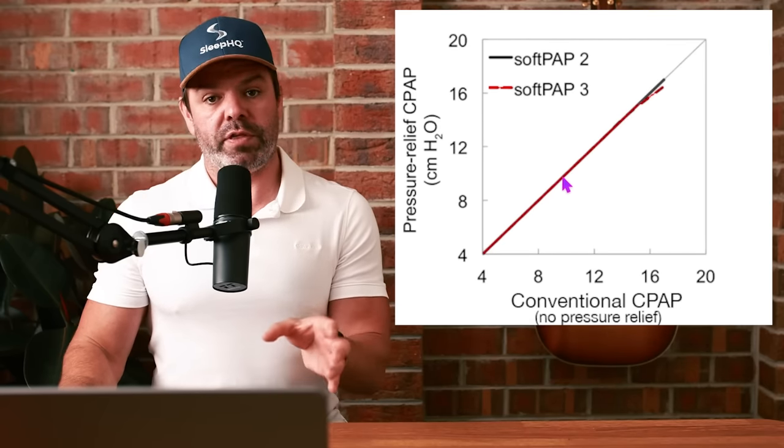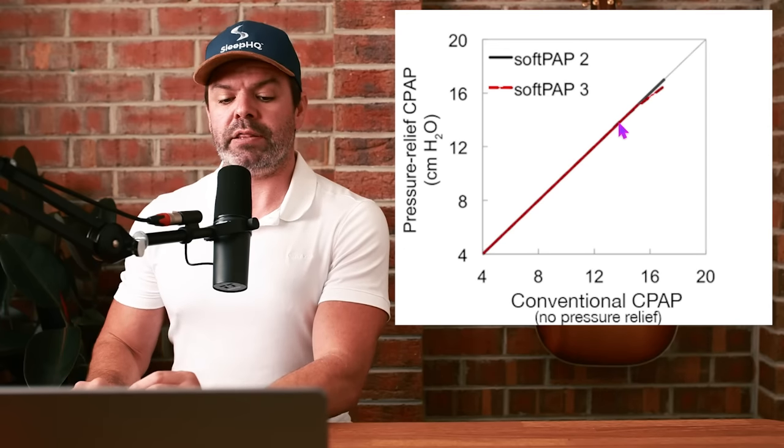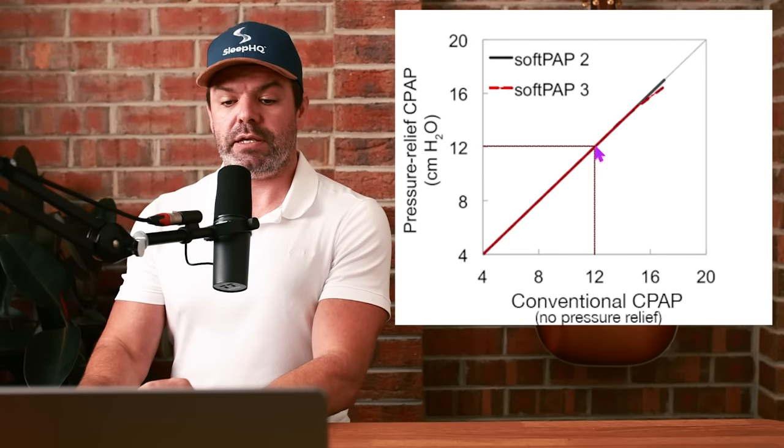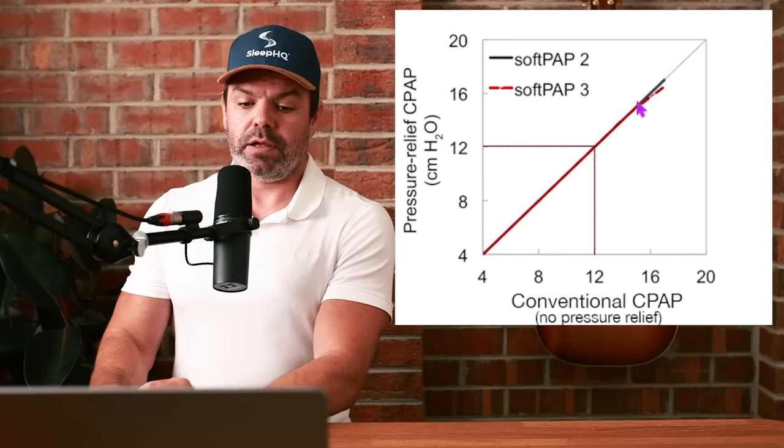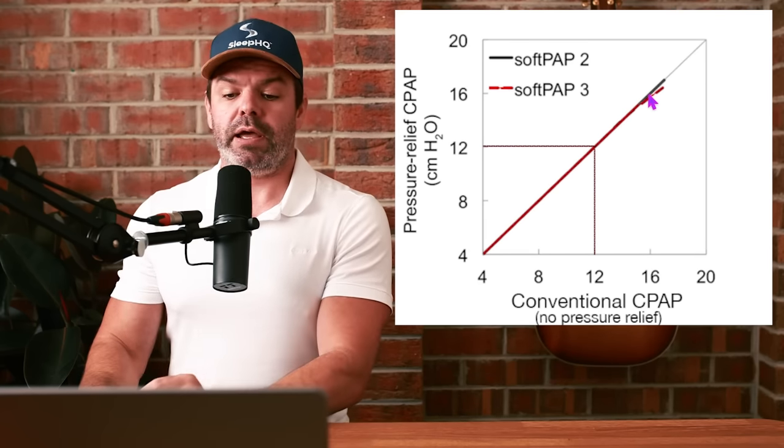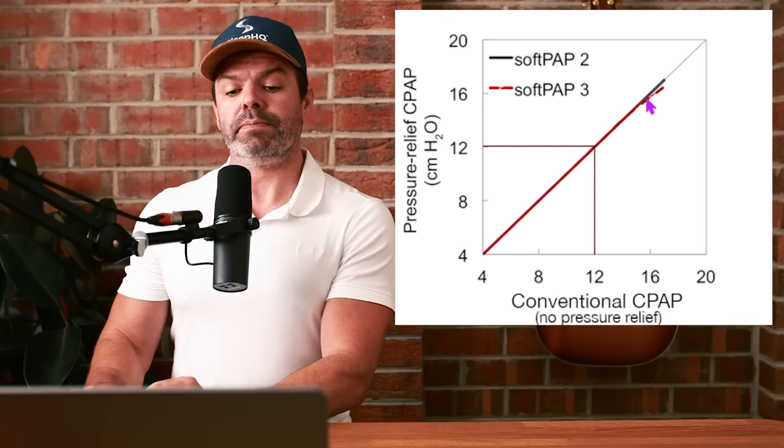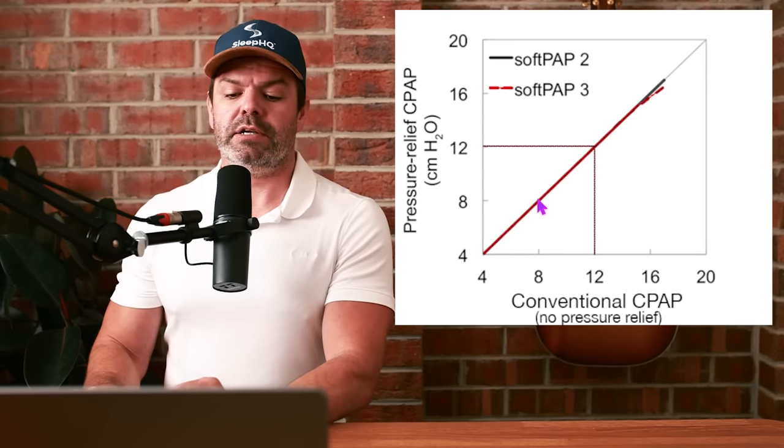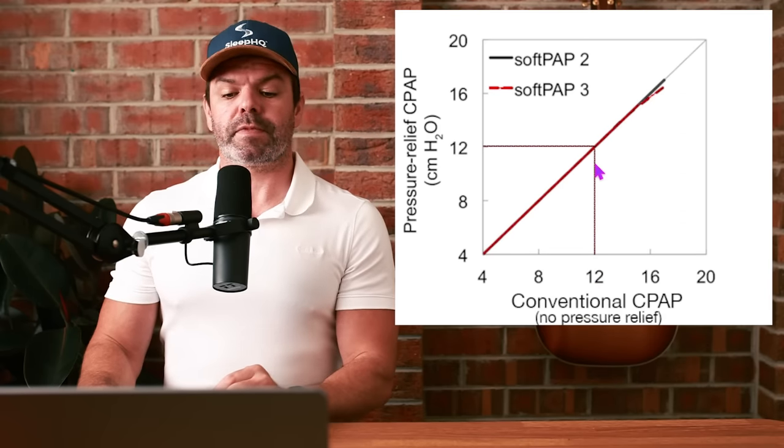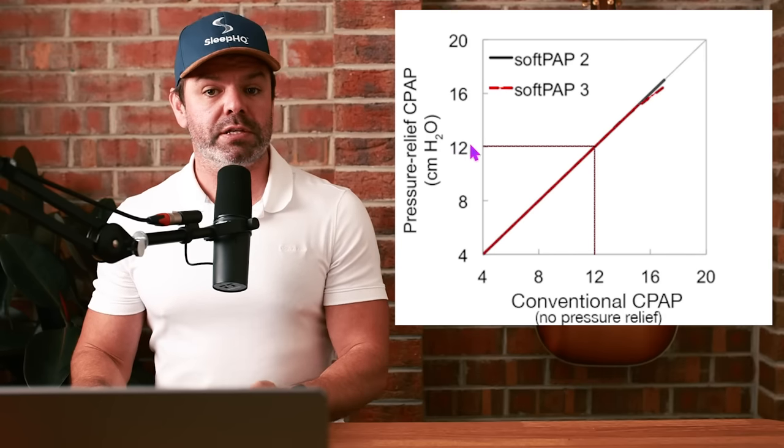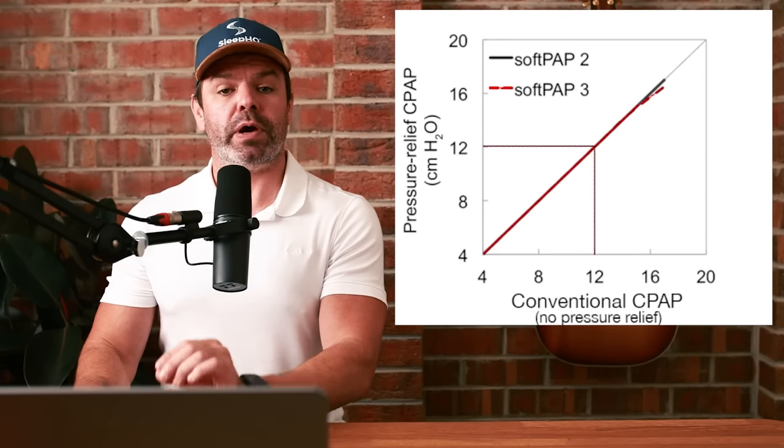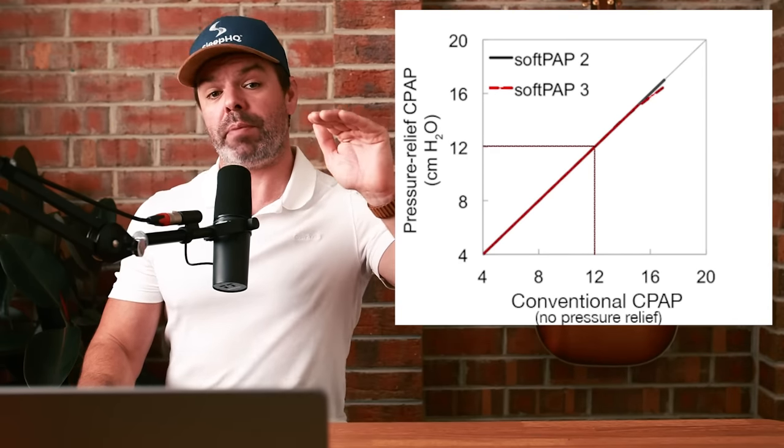to that with SoftPAP on two and three. Here's 12, you can see the lines here. This little gray line runs right from here to here. This is the conventional CPAP pressure required, and then we've got the black line and the red dotted line. The lines are very, very close together. So 12 centimeters with conventional CPAP no pressure relief is the same as 12 centimeters with pressure relief. You can have your cake and eat it too. You can have SoftPAP on two and three and you don't have to adjust that CPAP pressure higher.